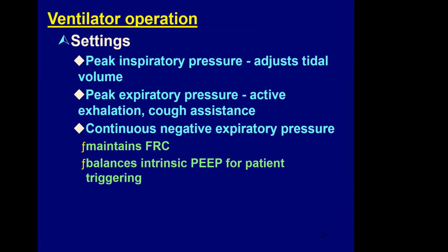Okay, the settings on these ventilators. The peak inspiratory pressure adjusts the patient's tidal volume. The peak expiratory pressure provides active exhalation and provides assistance with the cough. The continuous negative expiratory pressure helps to maintain the patient's FRC and also balances any intrinsic PEEP to allow patient triggering.